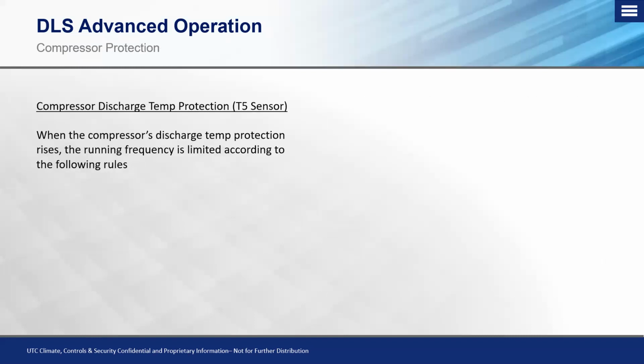So taking a look at our first temperature sensor, which is going to be our compressor discharge temperature protection. This is going to be our T5 sensor. So when the compressor's discharge temperature protection rises, the running frequency is limited according to the following rules. So essentially what that means in layman's terms is as that temperature on the T5 starts going up to a certain degree, the system realizes that and says, hey, I'm getting too hot. I'm going to throw countermeasures. Do I need to slow the compressor down? Do I need to increase or decrease fan speed? Do I need to adjust my valve positioning or my EXV positioning at the outdoor unit to try to bring that temperature down to protect that oil from carbonizing?